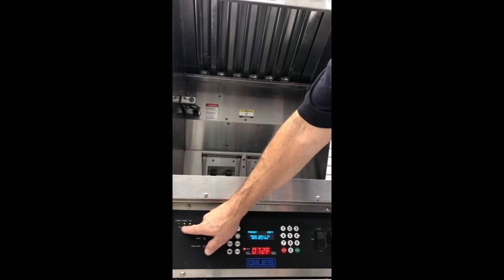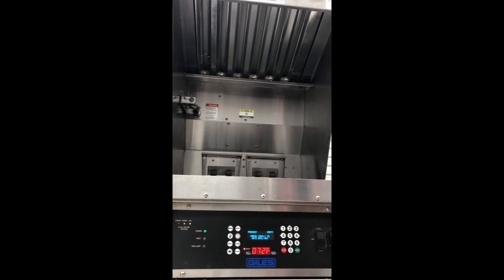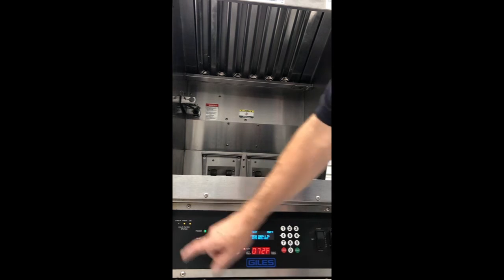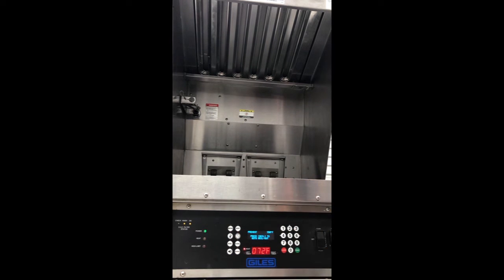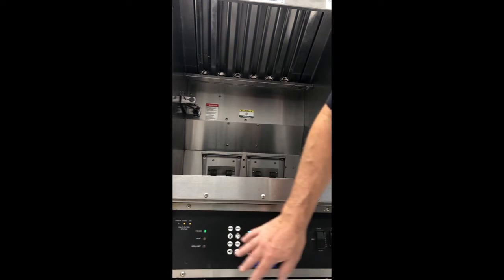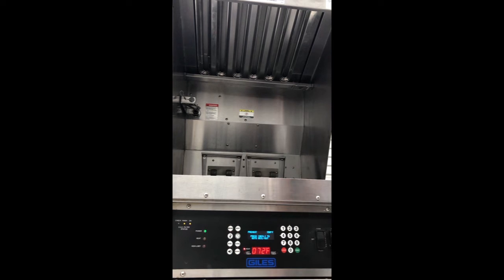When you see this wash light come on with this on light, you're going to go into alarm in just a little bit. You've got about 90 seconds. If this wash light stays on, you're going to get an error message here, and it's going to shut your heat off. On your larger units, larger hoods, they have the same system, but they shut off all the equipment underneath if they're wired correctly.